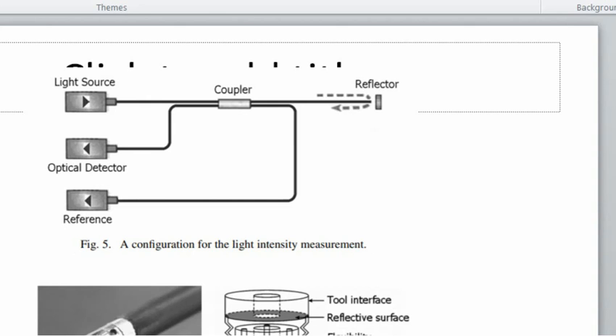Electrical wires are not suitable for use in MR environments since they usually induce eddy currents and magnetic fields, disturbing the MRI signal. However, such robotic systems for sensing information would be essential. Unfortunately, most force sensors containing electrical components cannot be employed in MR environments. Sensing force with optical fiber is one of the only feasible methods that can be practically applied.